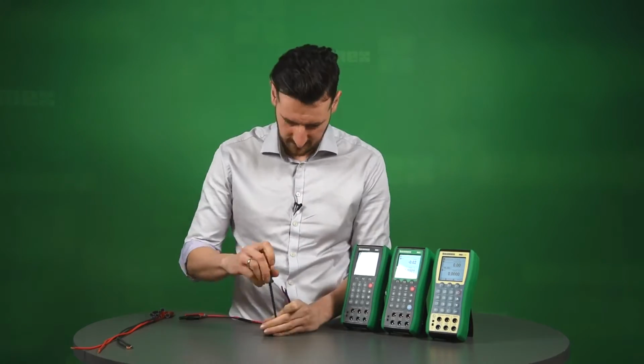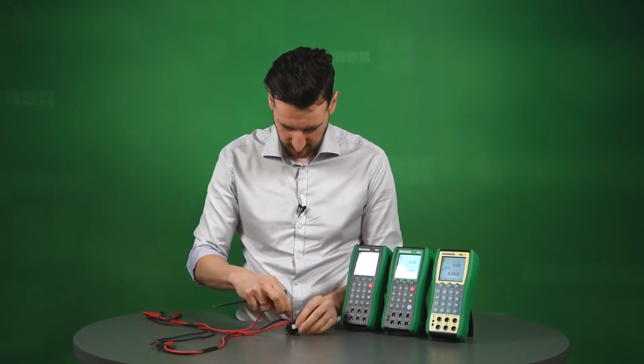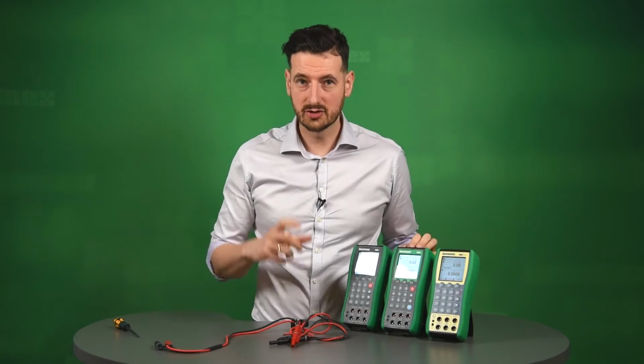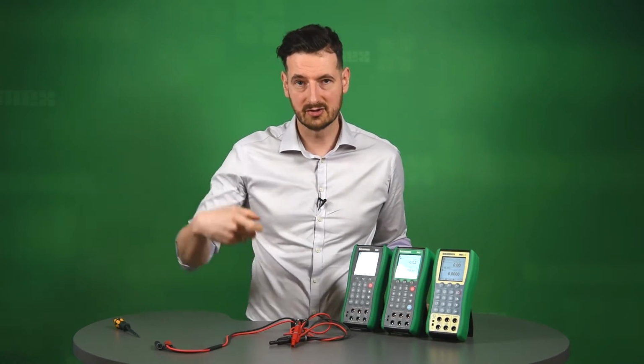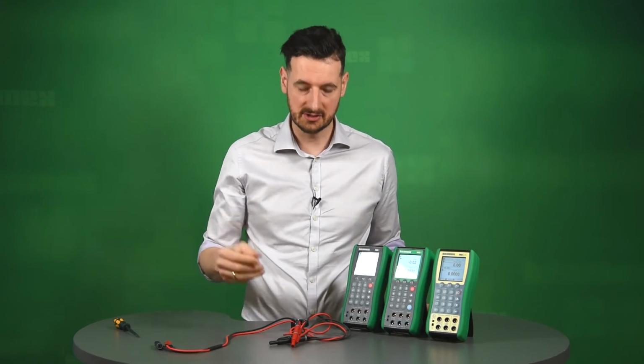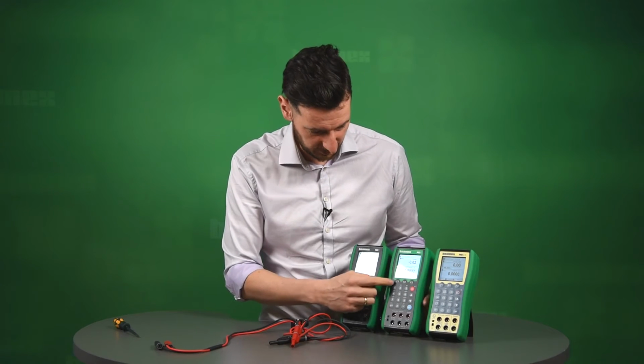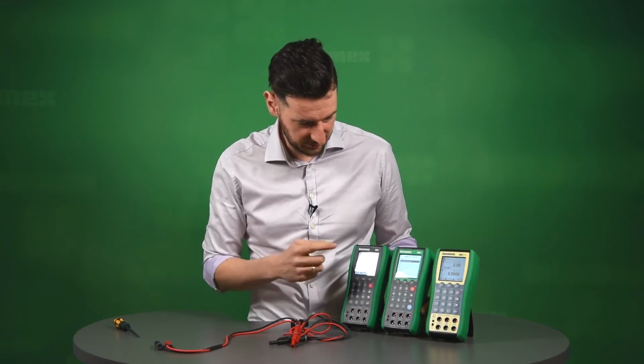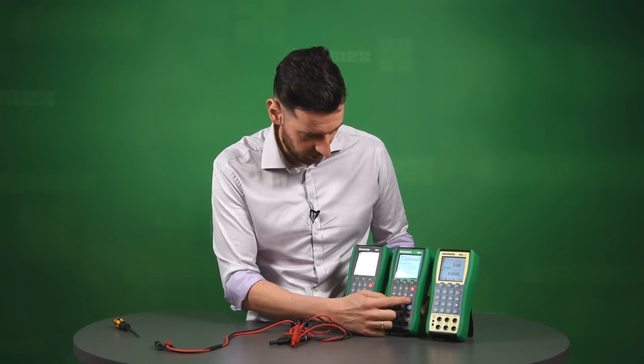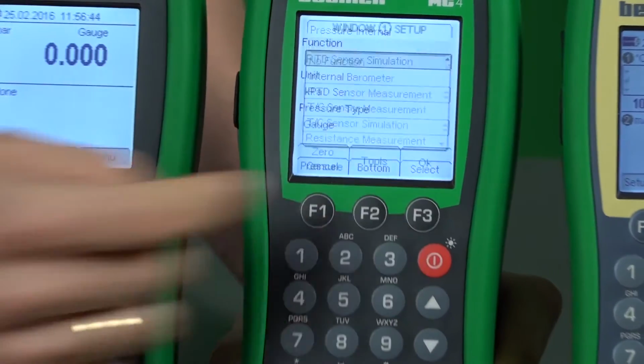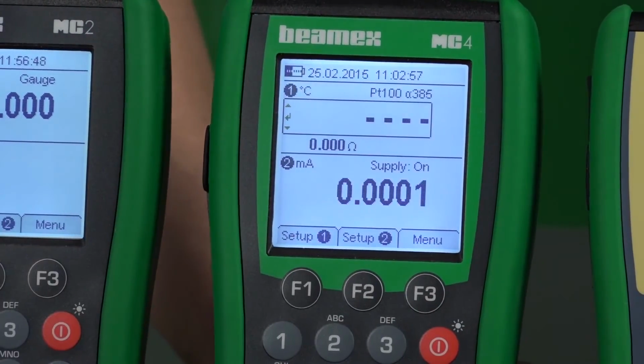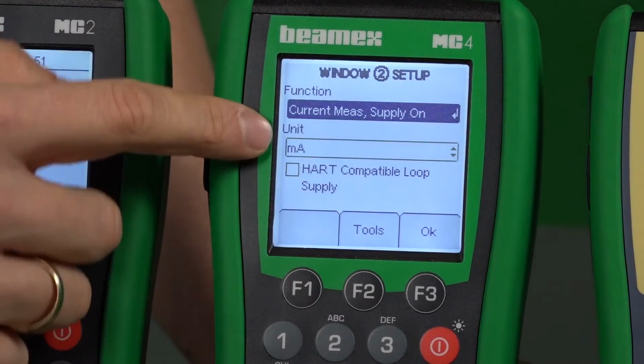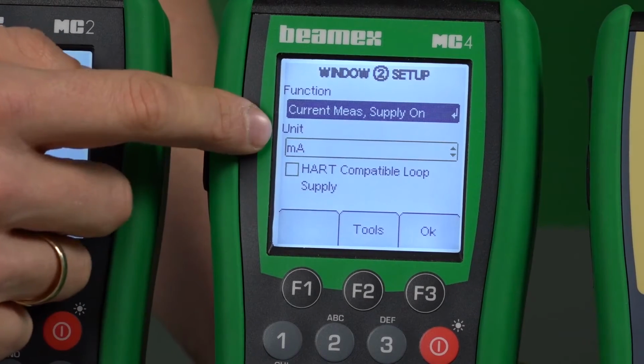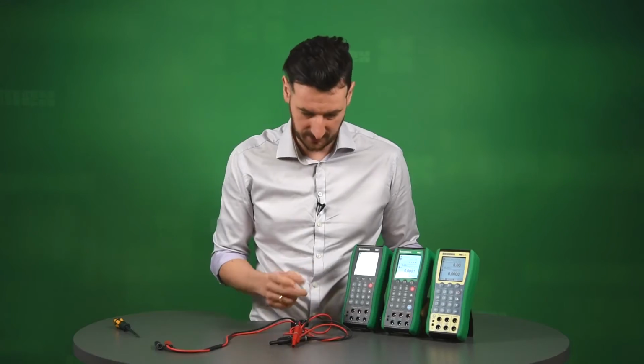So let me connect the test leads to our transmitter. I'll see you in a minute. For the purpose of this video, we're going to use the MC4 and we're going to document the whole process so we can also send it back to our calibration management software. On the MC4, we're going to set this up first. On our window 1, we are going to choose RTD sensor simulation. And on our window number 2, we already selected current measurement with the supply on, and we're going to measure that with milliamps. So I have to connect it right now.